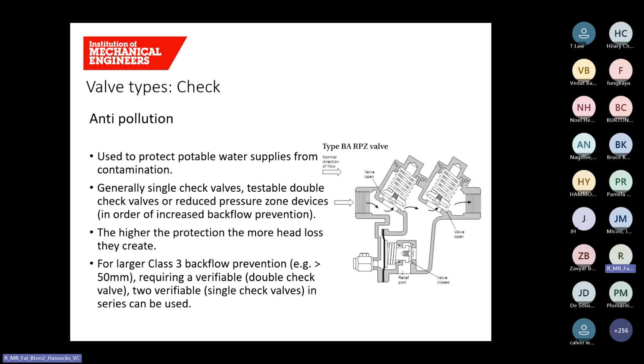Check valves are also used for anti-pollution. So where you've got a connection into a potable water network, there's a risk of contamination depending on where that feed's going to. So it might be going to a sludge plant, it might be going to a domestic supply, it might be going to a washdown hose. So depending on the risk of that use, you would select an appropriate measure of backflow prevention. The lowest control measure would be a single check valve, and then the next level would be two check valves in series with a bleed point in between, just to verify that you've got protection, that the valve is working. And then the highest level of backflow prevention using a valve is the reduced pressure zone device, and that's shown on the screen on the right here.